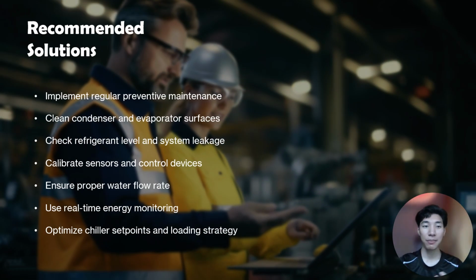Okay, so the recommended solution is to implement regular preventive maintenance and clean the condenser and evaporator surfaces. Next, check refrigerant level and system leakage. Calibrate sensors and control devices. Also, we ensure proper water flow rates, use real-time energy monitoring, and optimize setpoints and control strategies.